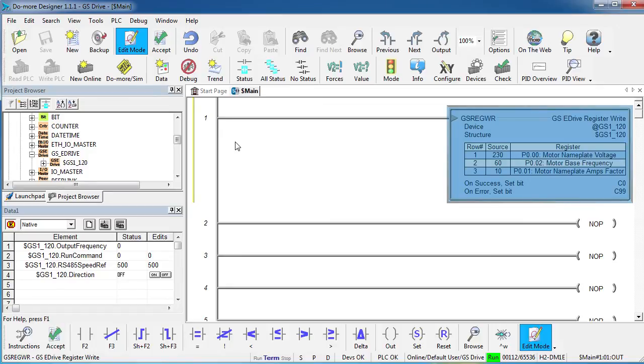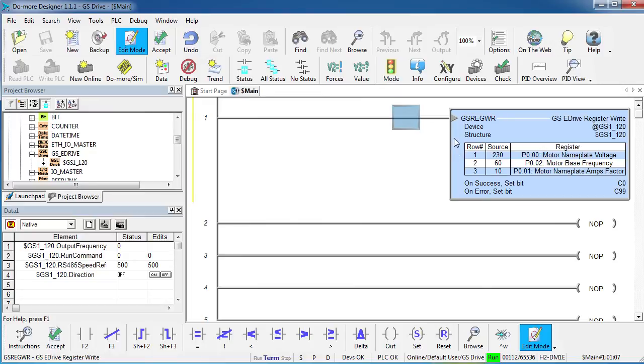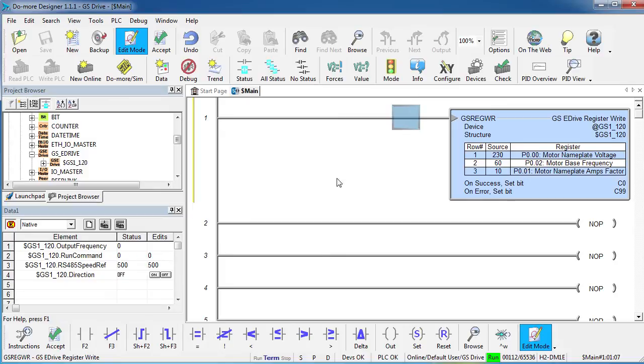Well, that's it, in one instruction I can configure my drive. And look at this, because this instruction is edge triggered, I don't even really need a contact here, right? The first time the program runs, this will see the rising edge, it will execute that and it will never execute it again. Or I could put a contact here and say only do this on first scan or I could even just drop this into an initialization routine that has a bunch of these for all my different drives. Lots of things I could do, but it's all set up to make it easy for you.